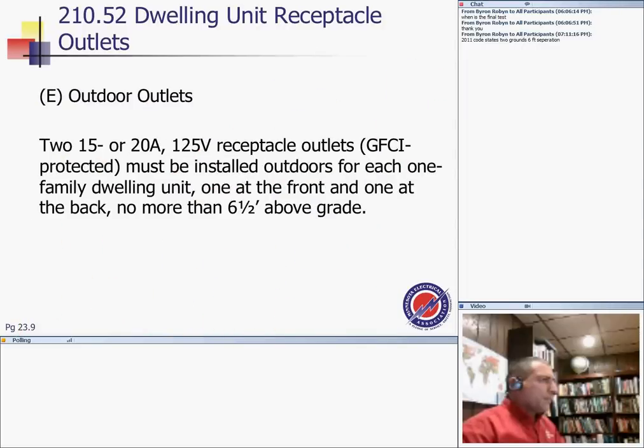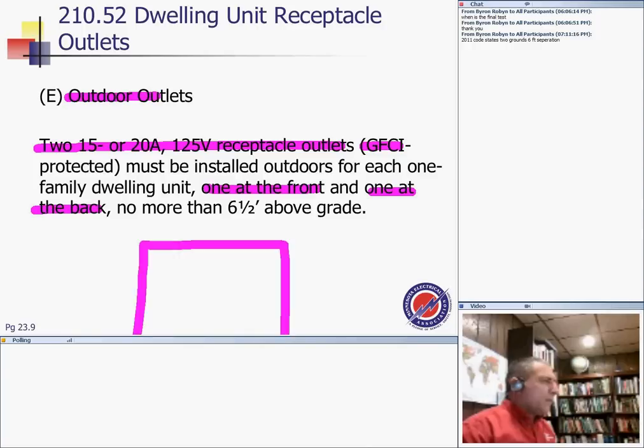Outdoor, we all say you need two 15 or 20 amp receptacles. They have to be GFCI, weatherproof. Oh wait, everything outdoors has to be weatherproof, GFCI, tamper resistant, right? And one at the front, one at the back. So you have a building here, the receptacle right on this side, and I mean single family and two family dwelling, one receptacle here, one receptacle here.